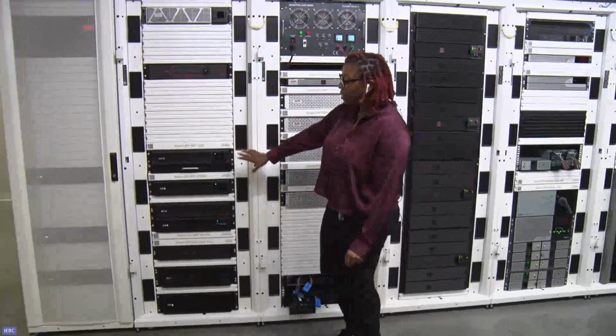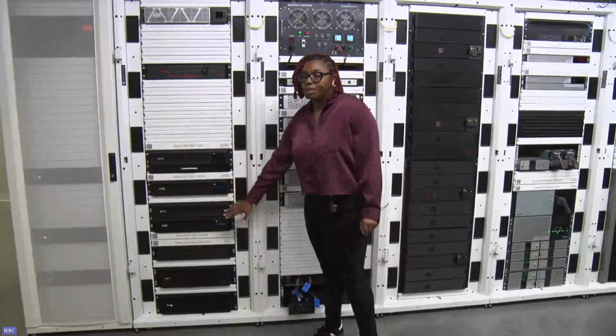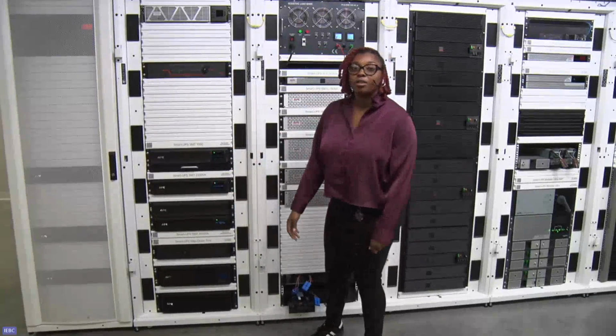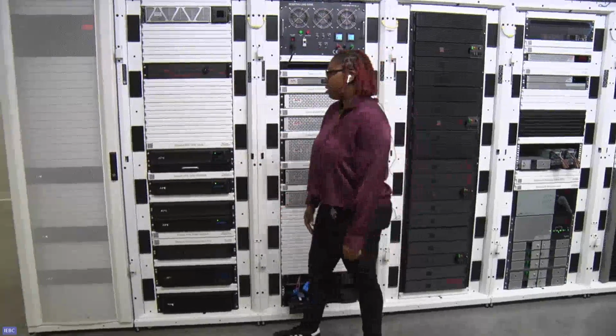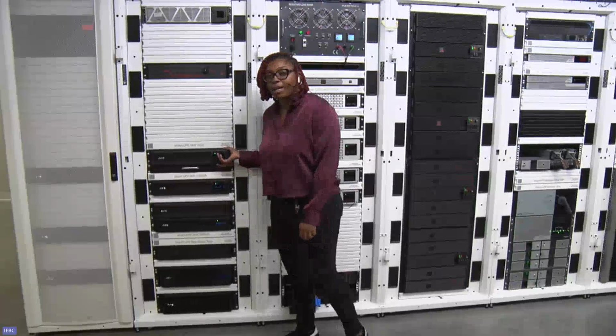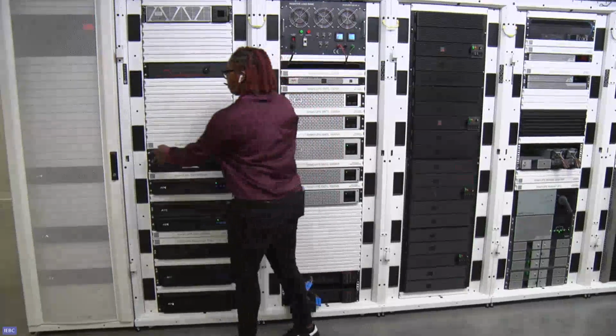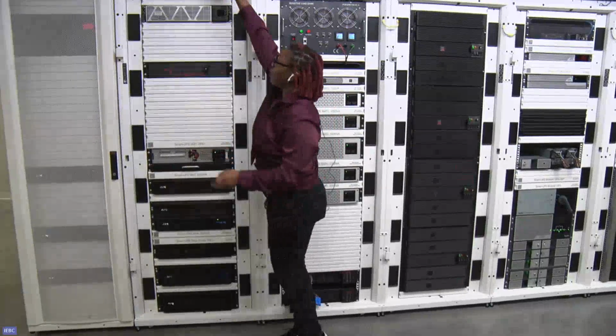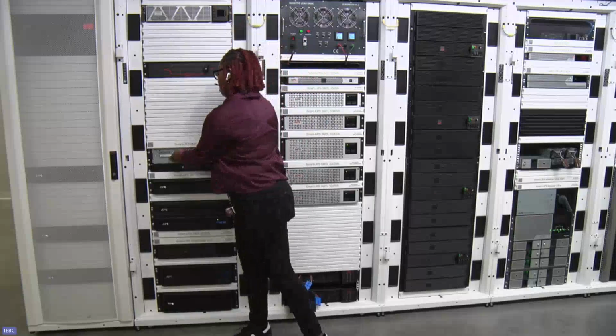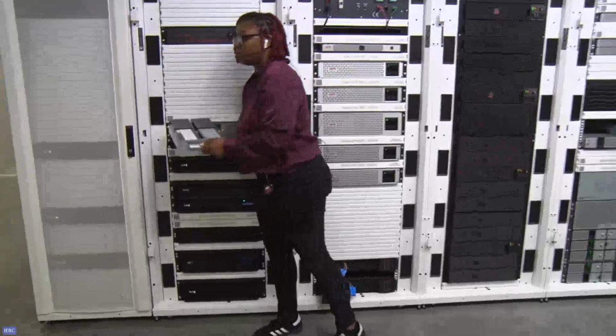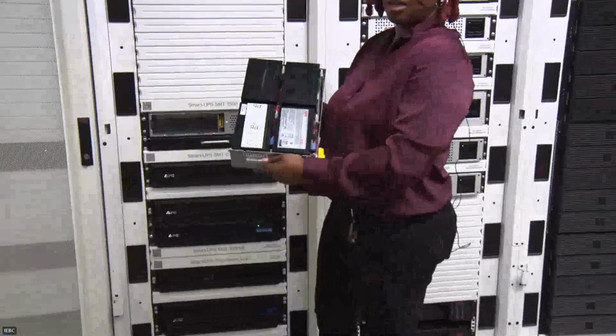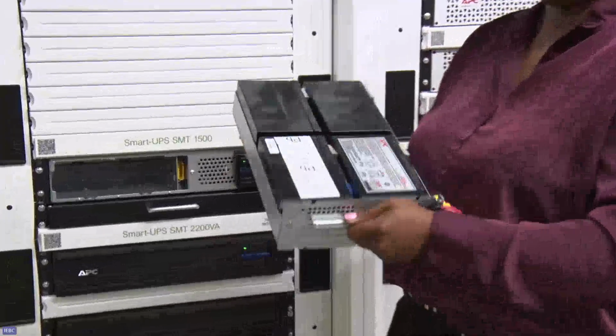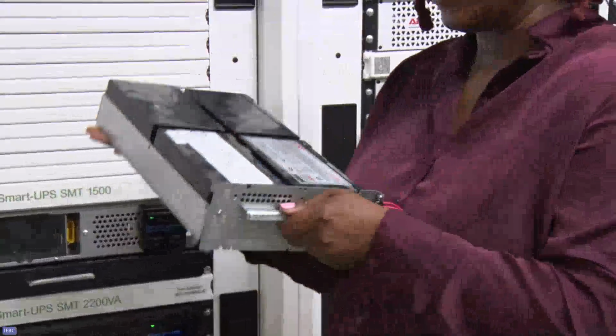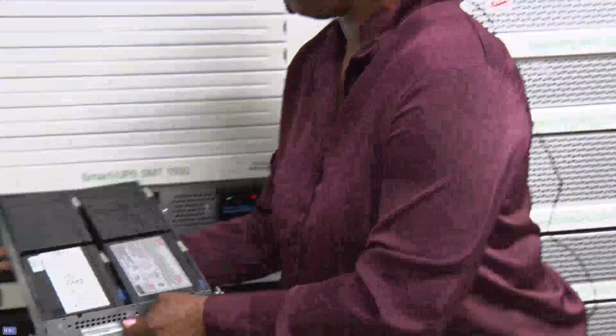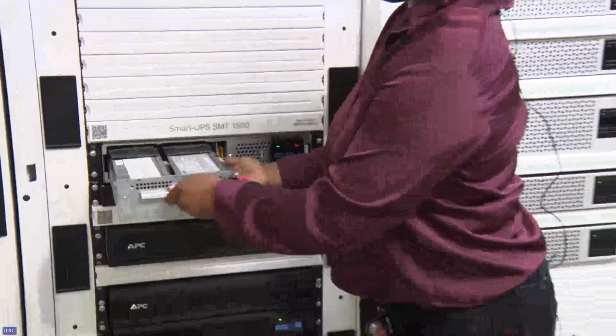These here, back to these UPS systems, if you see they have the black covers, these have our traditional battery solutions. So that's our valve regulated lead acid batteries, VRLAs. You can take this cover off, and this is what this battery looks like. It's actually quite heavy. I do this quite often, so you can't tell, but that's what our VRLA looks like.